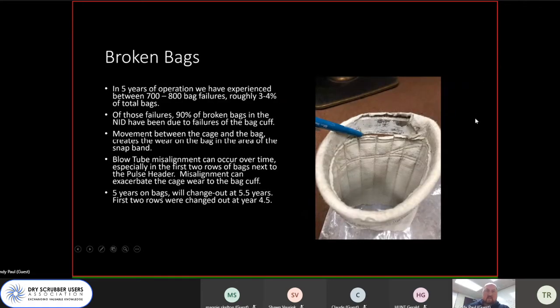What we've experienced is a relatively high volume of bag failures. In 5 years of operation, we've had 3 to 4% of our bags fail, and we've seen the vast majority of those failures at the cuff where it comes in contact with the snap ring, which is part of the bag cage. We get a lot of wear between the snap ring and the cuff when we're pulsing those bags.